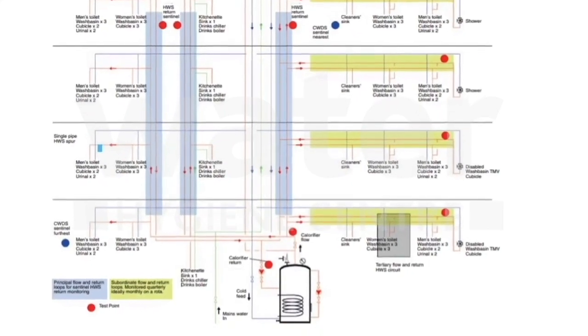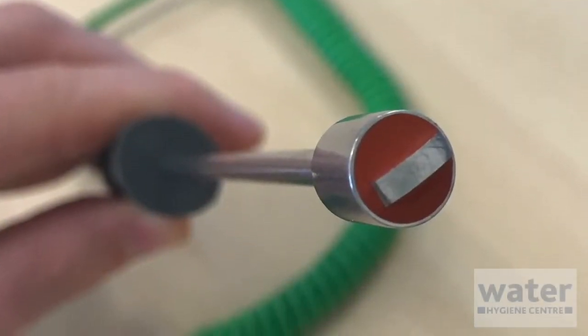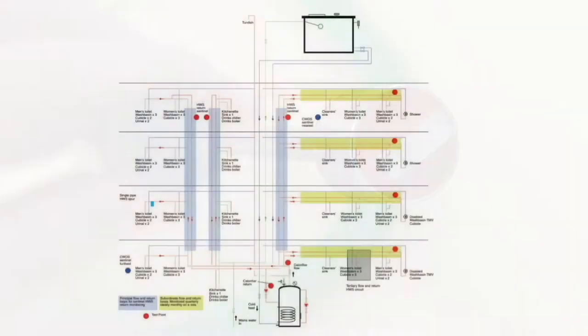If your building has a recirculating hot water system, you will need to use a surface probe to take temperatures from the correct loop locations, as demonstrated here in HSG 274 Part 2. More complex systems may require principal, secondary, and tertiary loops, which will all require monitoring.